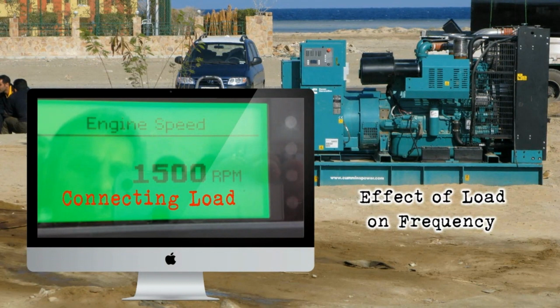This is very fast because this generator has a governor. Normally, modern diesel generators will have an electronic governor, very fast. But I made the video slow for you. You will see how the speed will go down. It will come back to the speed again by the action of the governor. If we don't have this governor, the speed will be kept at its lowest figure. Next, when we remove the load, you will see that the speed will go up.